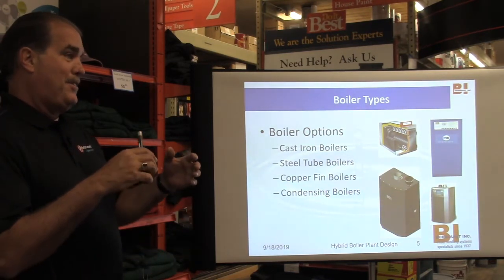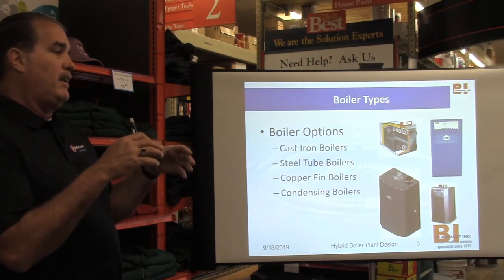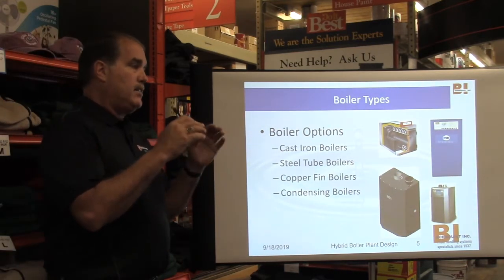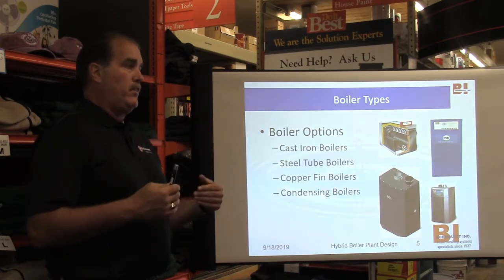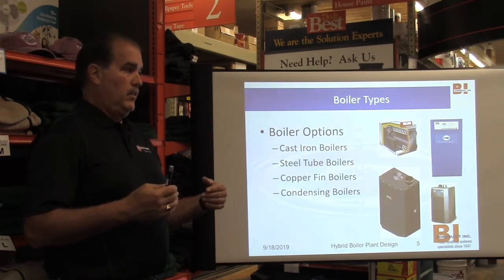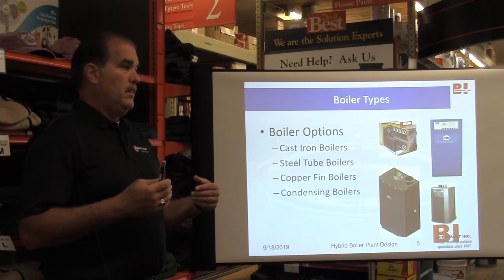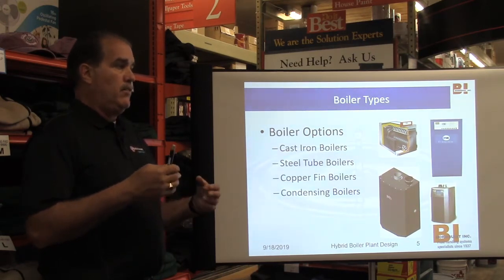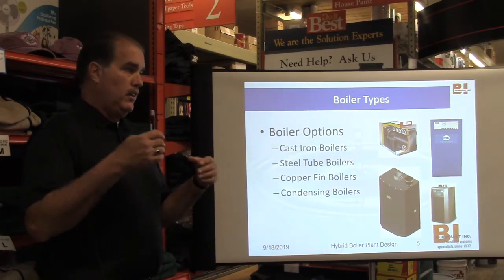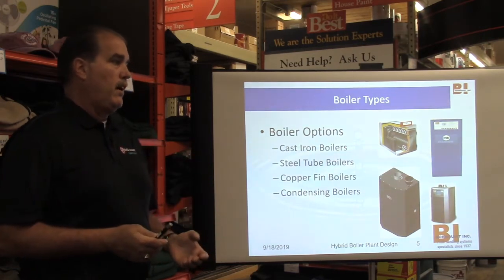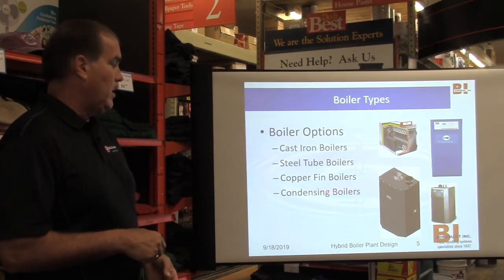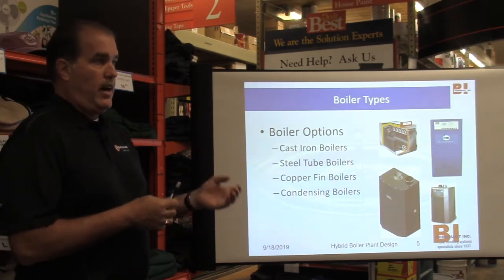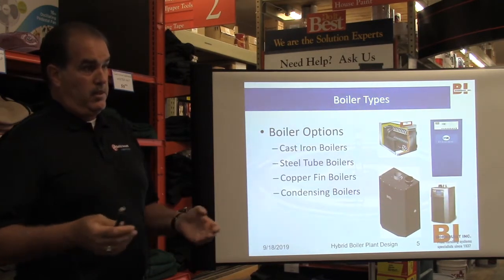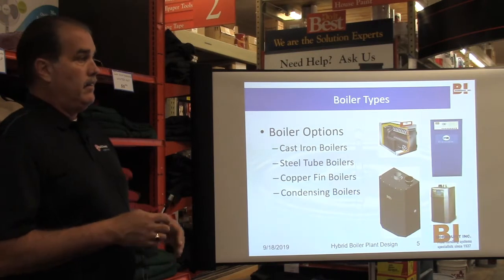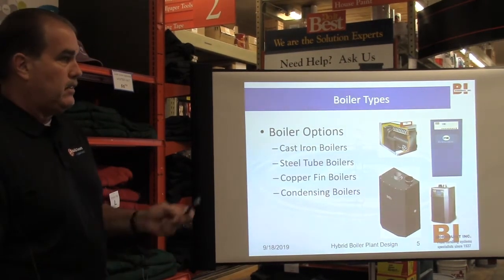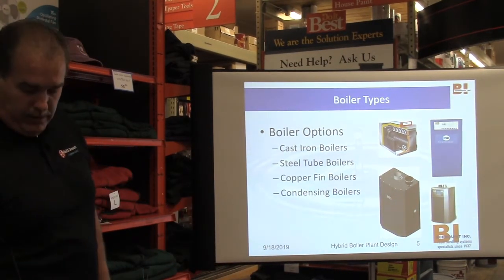I didn't want to get into this conversation too deeply because it's kind of complicated. But you're not going to save any money unless you can drop your water temperatures in the building down, so you're running cooler water temperatures. It's the only way you can condense. If your set point's 180 degrees, you're never going to condense, and there's no reason to have a condensing boiler because it's only going to run at 87% just like your non-condensing boiler, and you spend extra money for something you're not going to use. I really don't want to get into that too far because that's a whole other topic for another day.